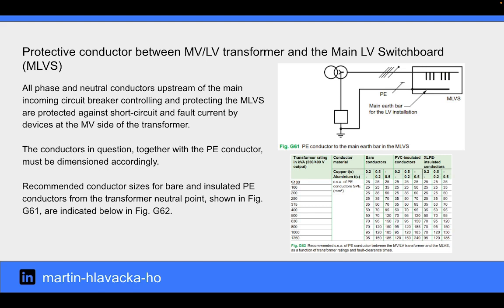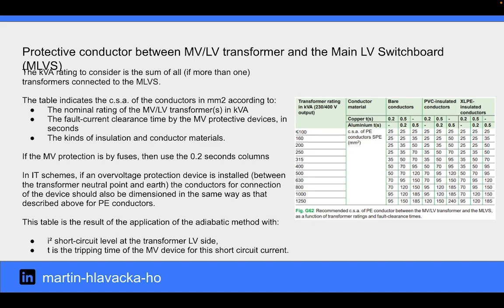Recommended conductor sizes for bare and insulated PE conductors from the transformer neutral point are indicated below in figure G61 and figure G62. The kVA rating to consider is the sum of all transformers connected to the MLVS.